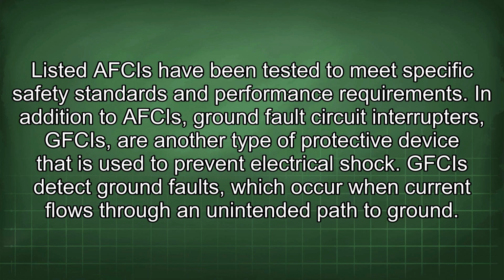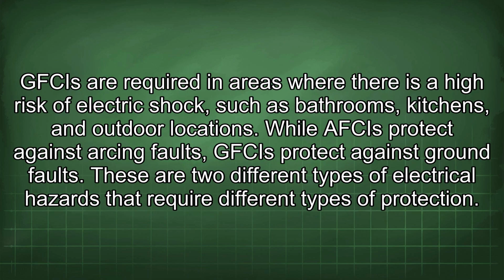In addition to AFCIs, ground fault circuit interrupters, GFCIs, are another type of protective device that is used to prevent electrical shock. GFCIs detect ground faults, which occur when current flows through an unintended path to ground. GFCIs are required in areas where there is a high risk of electric shock, such as bathrooms, kitchens, and outdoor locations. While AFCIs protect against arcing faults, GFCIs protect against ground faults. These are two different types of electrical hazards that require different types of protection.